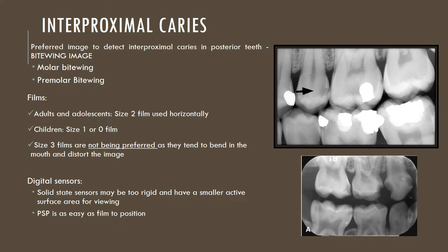Digital sensors — solid state sensors — may be too rigid and have a smaller active surface area for viewing, so placing them for bitwing radiographs may sometimes limit the visible area. A PSP, which is more similar to a film, is as easy to position as a film and is a more preferred choice for viewing interproximal caries on a bitwing. The images shown here are an adult bitwing showing the molar and part of a premolar region, with a proximal lesion visible on the distal surface of the maxillary premolar, and a bitwing of a child showing the right side involving the deciduous molars.